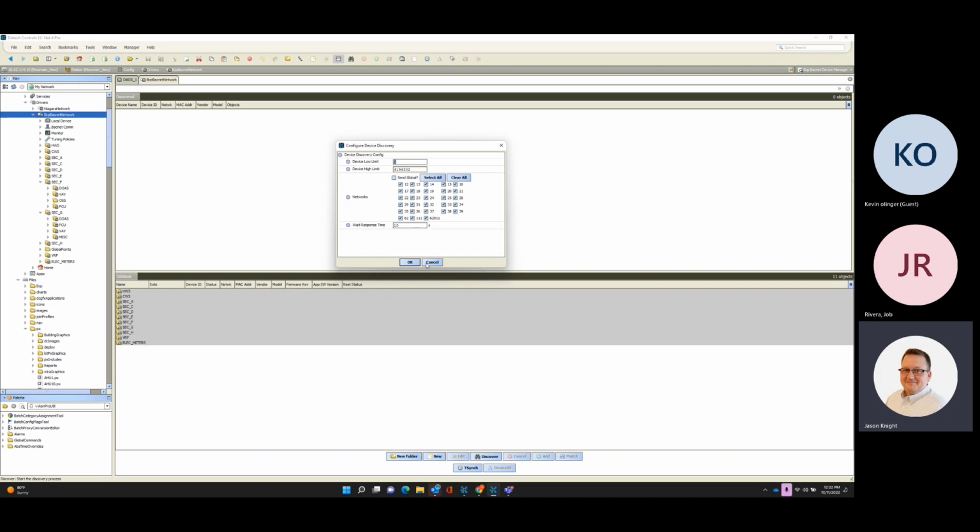All your IDF closets are all managed switches, routers, racks by your IT department. Your chilled water plant has a dumb switch, meaning it's not managed. It's just a physical Ethernet 10 by 100 megabit switch. That switch has an Ethernet cable pulled from your boiler plant, the physical mechanical room, I'll call it, over to the IDF room in Sector D. And this will be one of the things that we do on the physical walkthrough and show you guys.